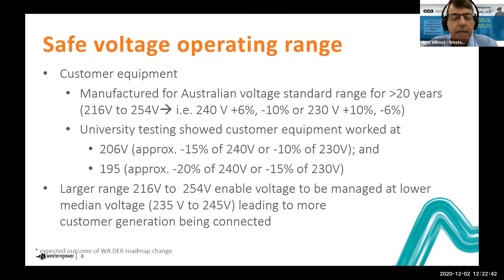The larger range will enable us to manage our voltage at a much lower level. Now, if you're not familiar with PV and the way we design networks, typically we design substations with voltage sitting just above 1 per unit on the MV level, and at the transformer LV terminals we sit at just under the upper limit to allow for voltage drop along our networks down to 240 volts or lower at peak times. As you're aware, things have changed. Now we have to repurpose our network for two-way power flow. And you can see in this example that when you connect PV at 100% hosting capacity, it's not much reverse flow that will then cause us to have a voltage which exceeds our limit of +6% or 254 volts.